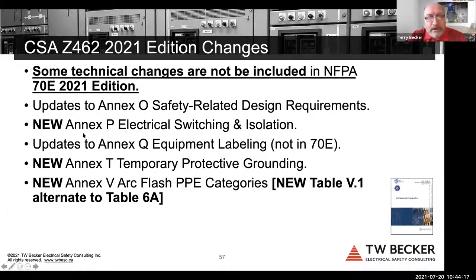So here are the annexes we added for high voltage: Annex P, electrical switching and isolation, and Annex T, temporary protective grounding, and then that new Annex V for the second alternate arc flash PPE category table that was meant to be easier for a qualified person to use.